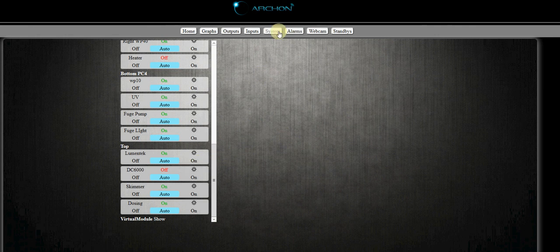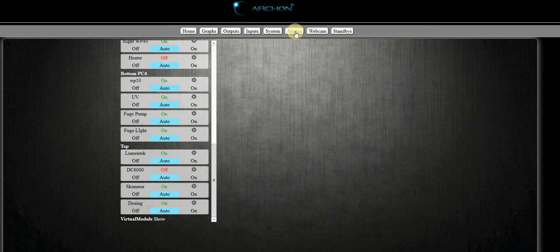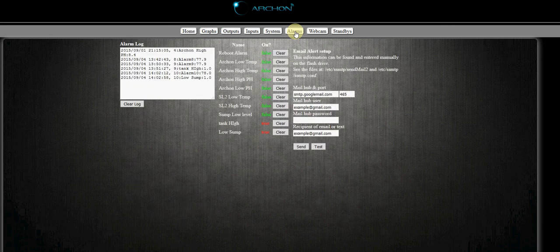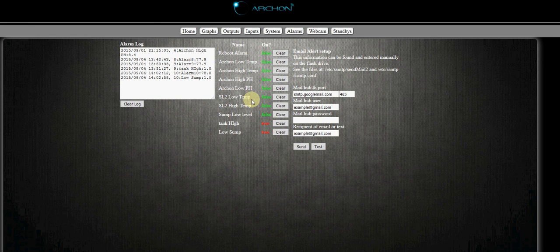Now to verify that, we can go over to the alarms tab. This will show us the state of that alarm. It should show that alarm is true and the color will turn red. You see right here that sump is low, so it is true.